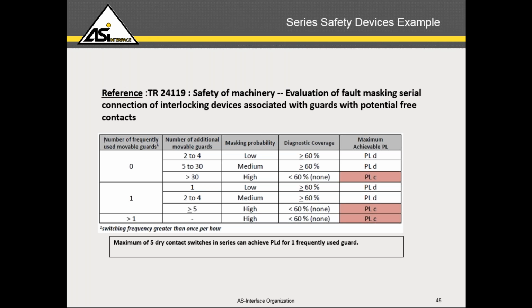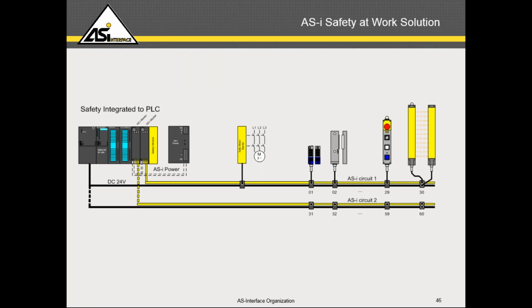So sometimes you may think you are getting something with the conventional way of wiring interlocking devices, but you may not be getting that. But with ASi, or the ASi interface with safety, it becomes a very simple solution, because the installation does not require complex engineering practices, and by default, the way Glenn explained it to you, it is a Category 4, Performance Level E solution. So all the interlock devices, the emergency stop, all the safety devices that you wire into the yellow cable, it's by default a Performance Level E, Category 4 safety solution.